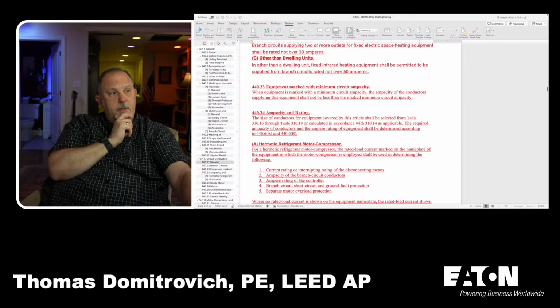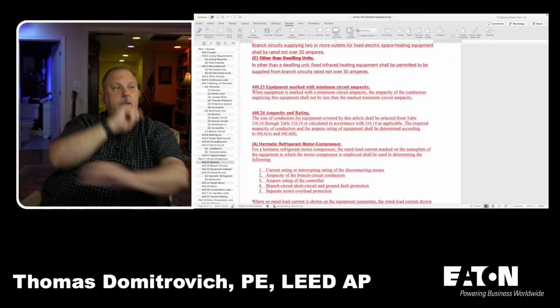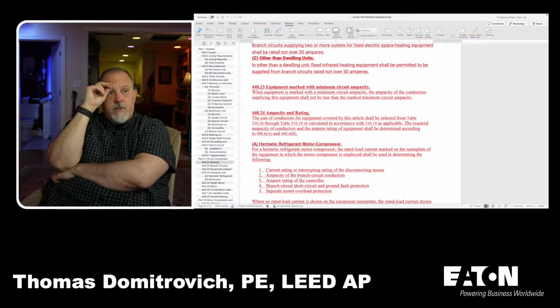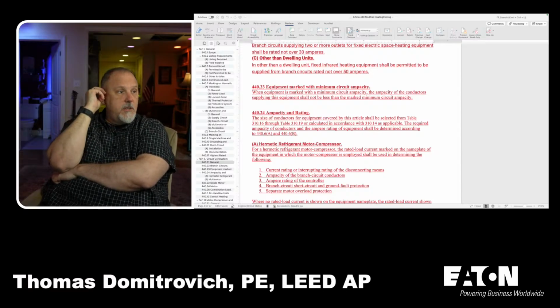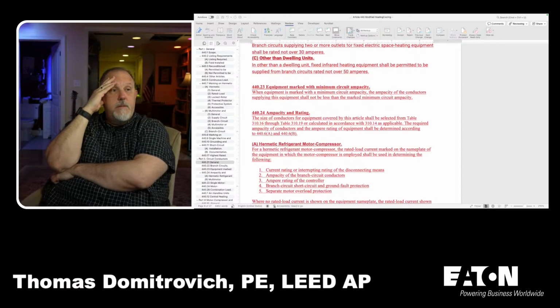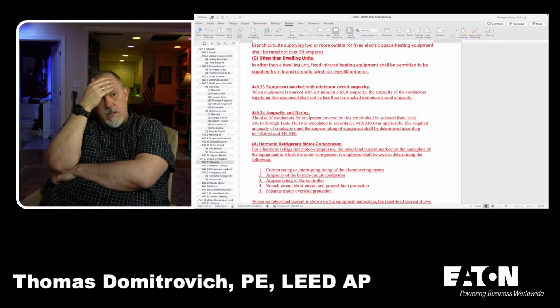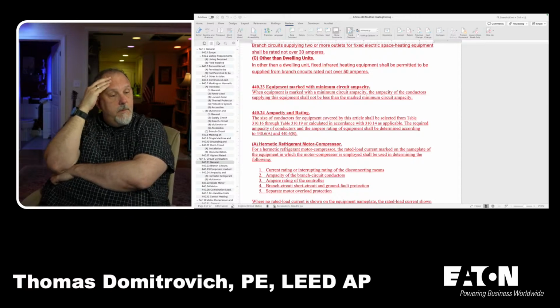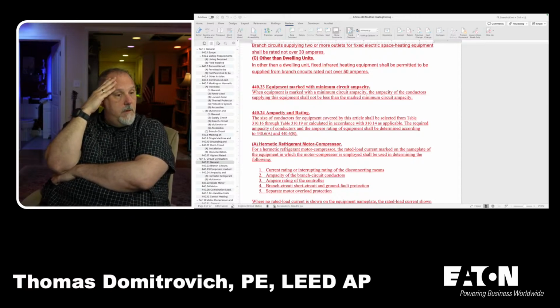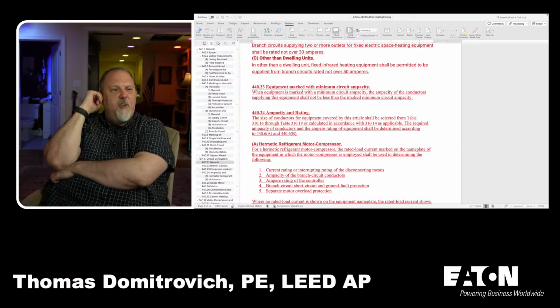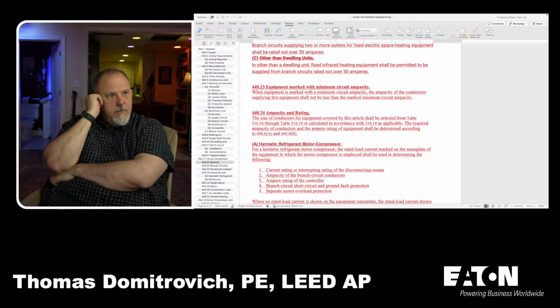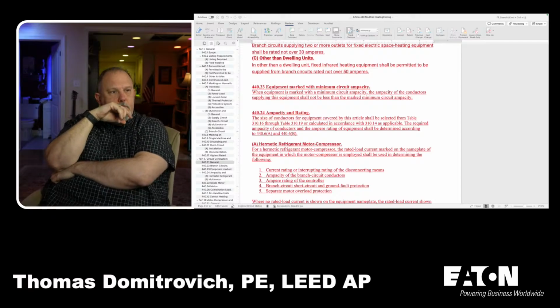440.23, equipment marked with a minimum circuit ampacity. When equipment is marked with a minimum circuit ampacity, the ampacity of the conductors supplying this equipment shall not be less than the marked minimum circuit ampacity. 440.24, ampacity and rating. When equipment is marked with a...